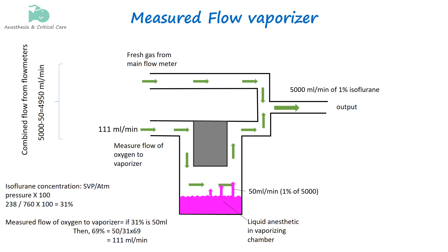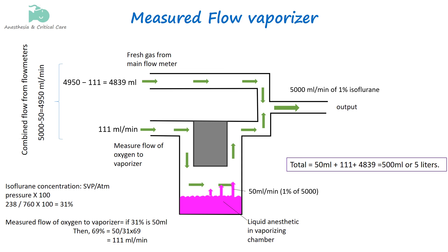This flow must be deducted from the total flow of 4950 mL/min so that the main flowmeter delivers 4839 mL/min. Adding the vapor flow, measured flow, and the fresh gas flow from the main flowmeter gives 5 liters per minute, which contains 50 mL of isoflurane representing 1% of the mixture.